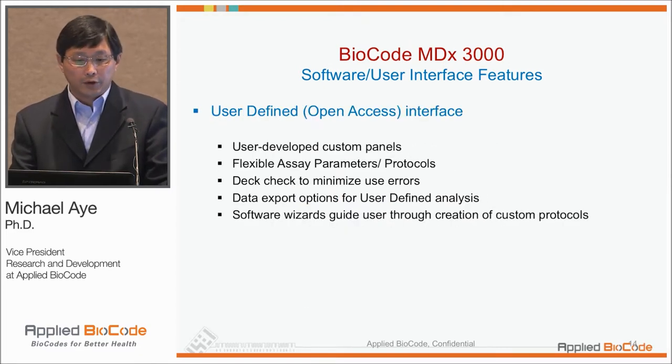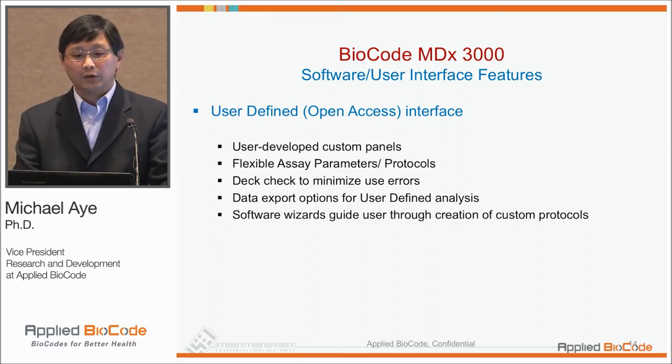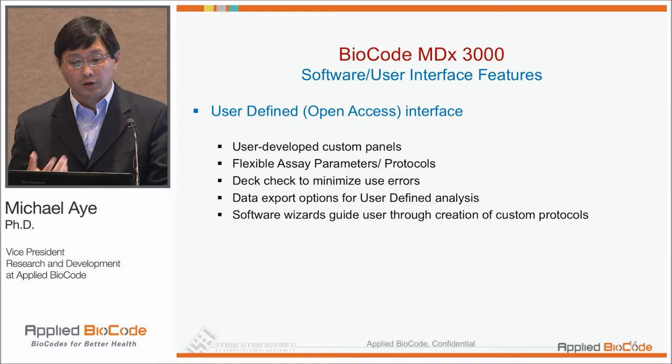The instrument has a Deck check program that verifies the consumables present on the deck, so that if a user makes a mistake, the Deck check will alert the user what needs to be removed or loaded. We also have an open access interface, and if you choose to develop tests on your own, you have flexible assay parameters and a software wizard that guides you through assay setup, along with Deck check and data export features.